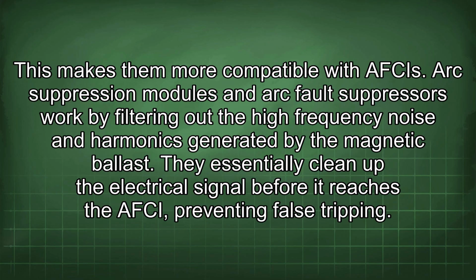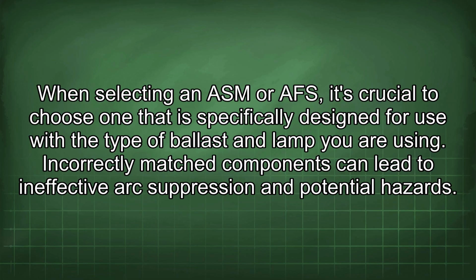Arc suppression modules and arc fault suppressors work by filtering out the high-frequency noise and harmonics generated by the magnetic ballast. They essentially clean up the electrical signal before it reaches the AFCI, preventing false tripping. When selecting an ASM or AFS, it's crucial to choose one that is specifically designed for use with the type of ballast and lamp you are using. Incorrectly matched components can lead to ineffective arc suppression and potential hazards.